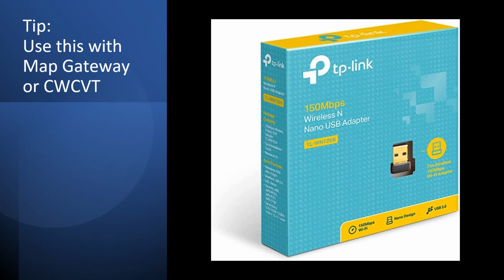If you do buy one of these, buy a slower speed one. Both the map gateway and the CWCVT tool are slow wireless in speed, so if you get a slower wireless adapter, you'll be matching those speeds. It's very helpful, especially if you've noticed that your computer drops the CWCVT tool or the map gateway randomly throughout the day. If it just keeps dropping, you have to keep connecting. Get you one of these little adapters and you won't have that problem anymore.